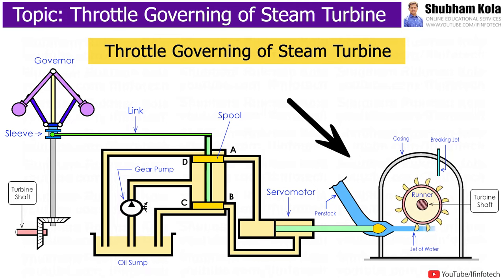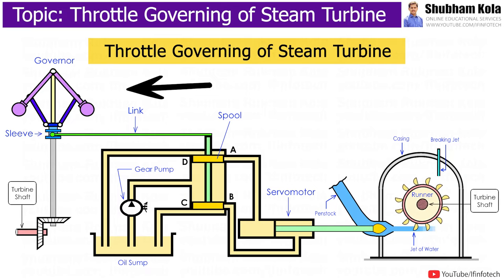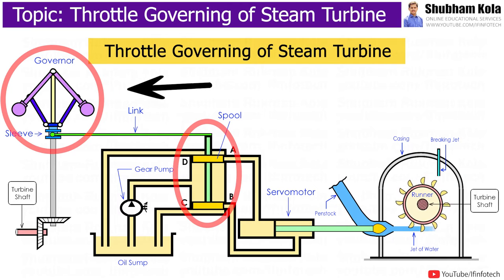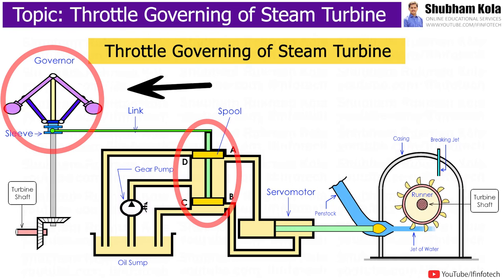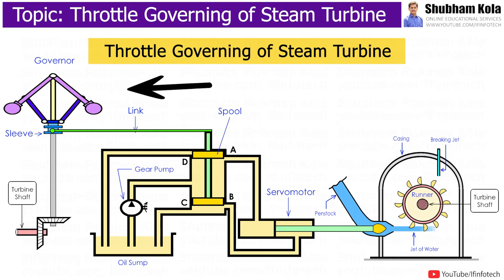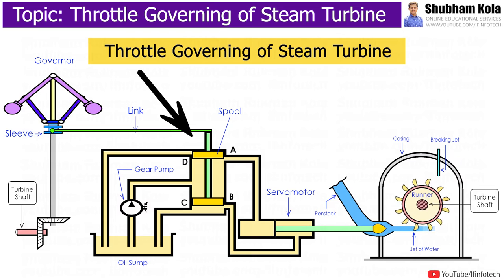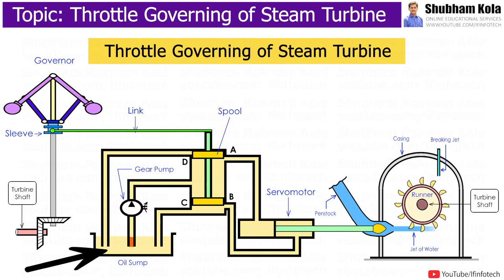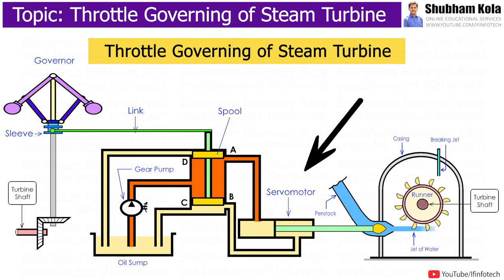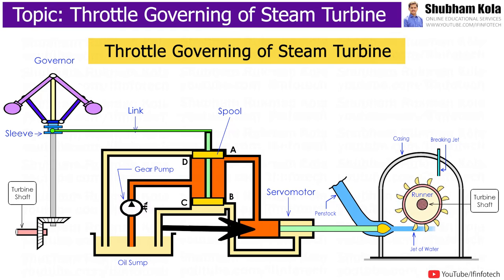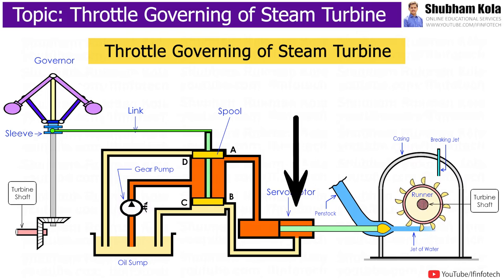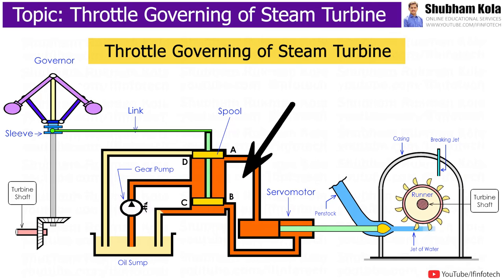Now let us assume the load on the generator is suddenly reduced. Since the power developed by the turbine is more than the load, the turbine and governor speeds will increase due to excess energy. The governor balls will fly out and raise the sleeve of the governor. Consequently, this link will pull the spool in the upward direction. The oil supplied under pressure will flow through pipe A to the servo motor, forcing the piston, while oil from the servo motor is drained out through pipe B.